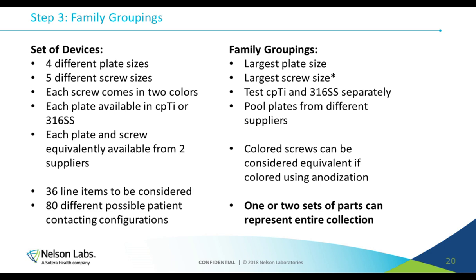And then from there, we had a group of titanium parts and a group of stainless steel parts. We said, okay, these different materials are made from different processes. We ought to test those as separate groups. So there is an opportunity: you could say, wait a second, maybe we could do just one test, take the largest titanium plate and the largest stainless steel plate and combine them together. But the more that you combine things together, you have to extract them in a way that they could fail if they had been tested separately. So the extraction pool becomes a lot more concentrated, and we tend to try to limit that as much as possible. So we said, let's test the titanium and the stainless steel parts separately.